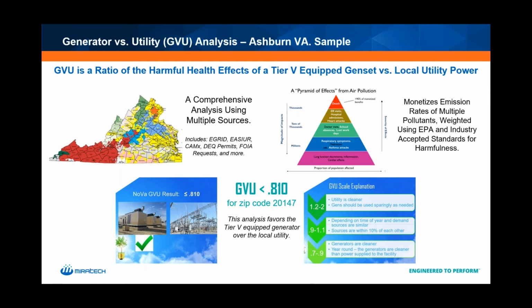With the parameter known as GVU, we're looking at how clean the generator is compared to the grid delivering power to the facility. Our first customer for this product was in Northern Virginia. We did about a 6-week analysis and came out with a 30-page report showing them what a GVU would be—comparing the generator to the Dominion-supplied power coming to the facility.